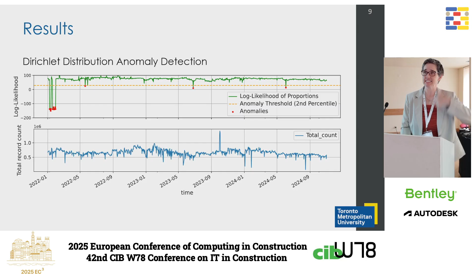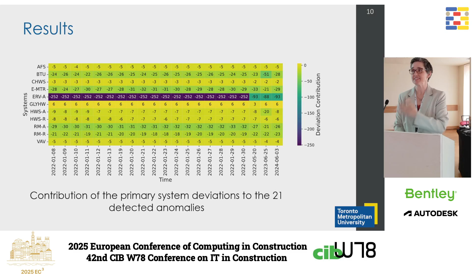But as soon as you see here, you actually have the power to see down at the system level, or if we were willing to implement it further, and this is what the Bayesian network is going to inform, if we find an issue here, then it can prompt a second set specifically for that subsystem, and then we can go down to the device. So we can say to facilities management, you have a sensor in this room that stopped communicating, which is going to mean the room's going to get too hot or too cold. If it's demand-controlled ventilation, you're not going to be ventilating it properly, et cetera. So it wound up being really important to keep track of that and communicate it properly to your facility manager so they know what to fix rather than just trying to generically fix everything.